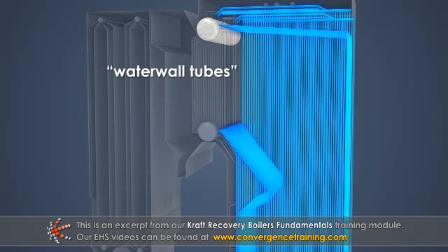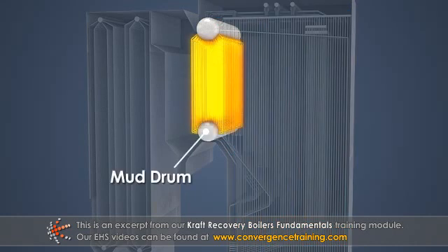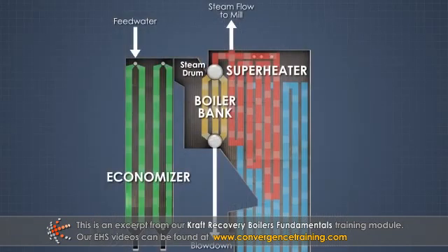The water wall tubes are part of the feed water circulation fed from the mud drum and steam drum system. The steam drum is connected to the mud drum by multiple boiler tubes. The mud drum also provides the blow down point where feed water impurities are continuously drained to the sewer through a small pipe.